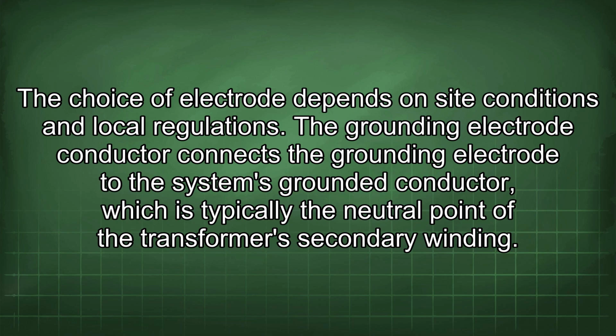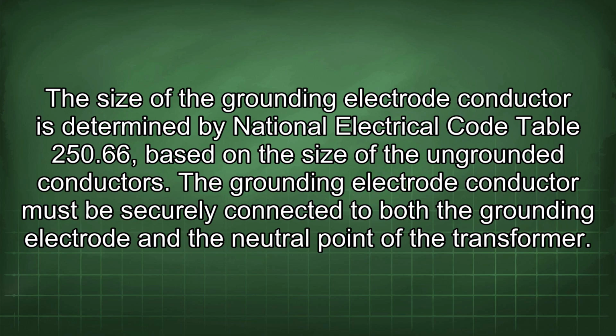The grounding electrode conductor connects the grounding electrode to the system's grounded conductor, which is typically the neutral point of the transformer's secondary winding. The size of the grounding electrode conductor is determined by National Electrical Code Table 250.66, based on the size of the ungrounded conductors. The grounding electrode conductor must be securely connected to both the grounding electrode and the neutral point of the transformer.